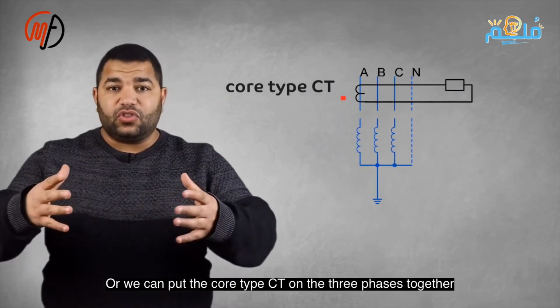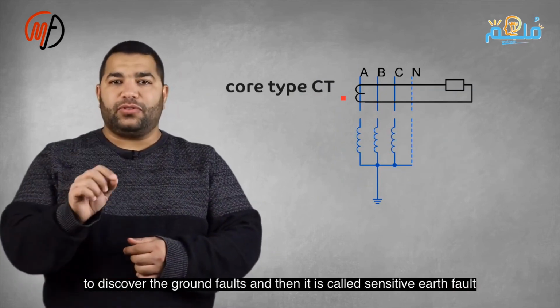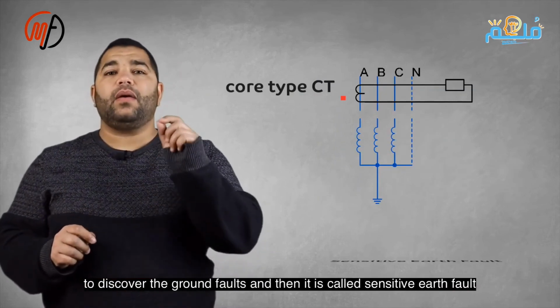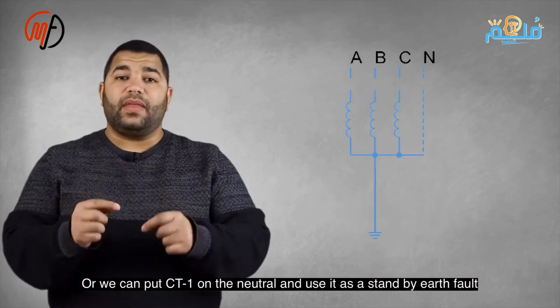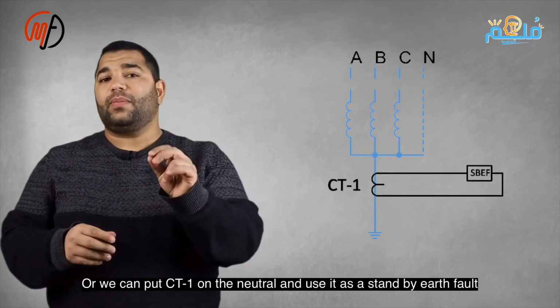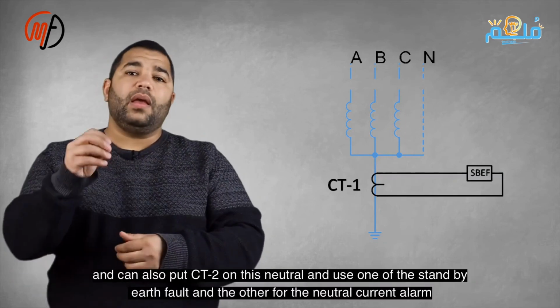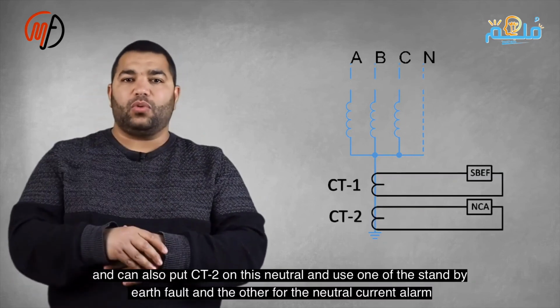Place one CT on the neutral for standby earth fault. Place two CTs on the neutral, one for standby earth fault, another for neutral current alarm. Note, the neutral current alarm doesn't trip the circuit breaker, it only alarms. It is more sensitive than standby earth fault, with a very low setting.